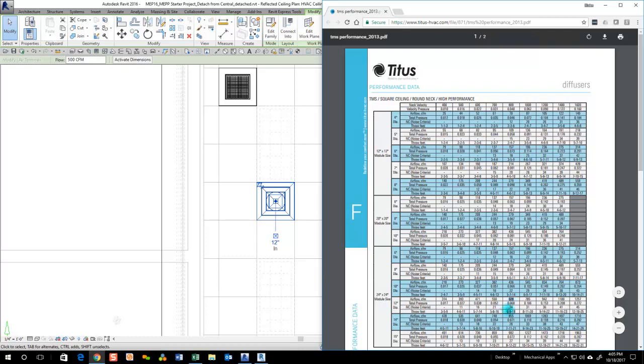Instead of reporting this data, because this is actually a bit oversized from what we actually want, now, and the user manual talks about this, we shift to the left and start checking values this way. Sure enough, this value meets the 500 CFM. This one does not. So I'm rounding up in all the cases. Essentially, the performance data now comes from this, as a better representation than this, when we're scheduling 500 CFM.